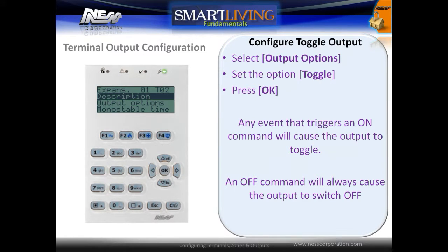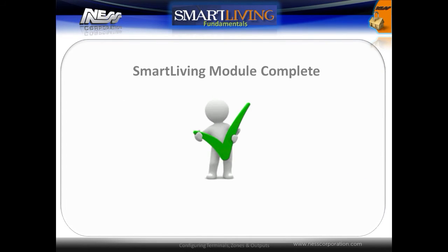To configure an output to be an on/off toggle output, select Output Options and set the option for Toggle. Press OK to save. Any event that causes the output to turn on will now toggle the output. An off command will always turn the output off. It is also possible to set an output as both mono stable and toggle at the same time — this will cause the output to toggle on and off but will only turn on for the mono stable time. This completes this training module.